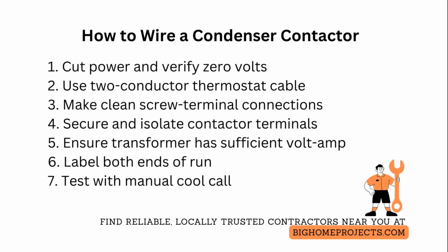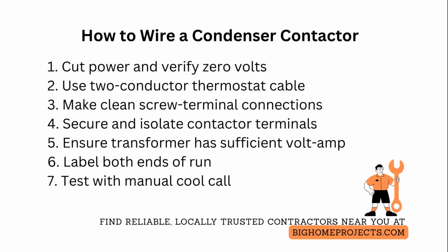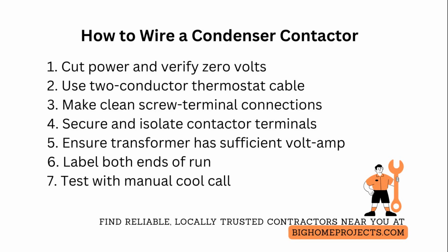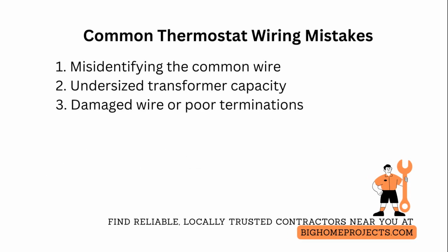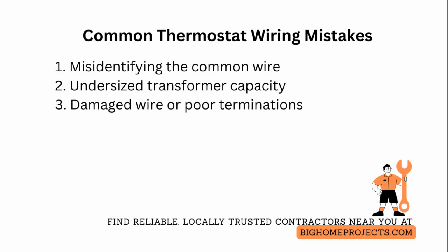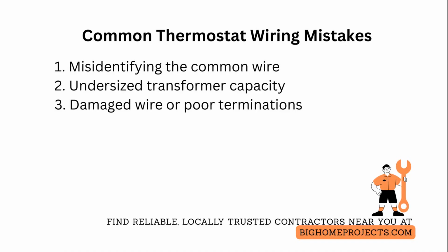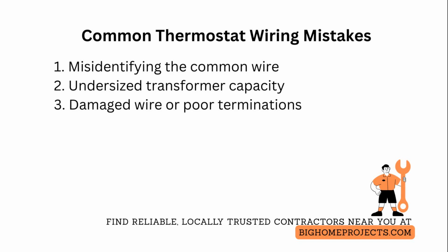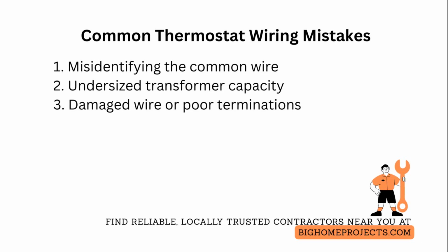After connection, restore power and operate a manual cool call while watching the contactor pull in and verifying 24 volts across the coil during the call. One of the most common thermostat wiring mistakes is misidentifying the common or C wire and accidentally tying it to a hot 24-volt or non-common terminal, causing blown fuses or unreliable thermostat power.